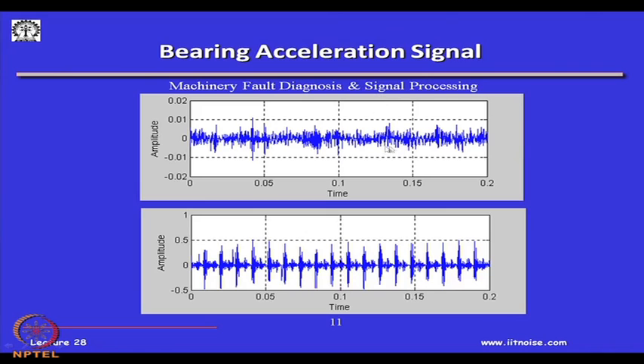And if you do the feature calculation from these signals, like the mean and RMS, you will see obviously the RMS value of this is much higher than this, but there are also factors like the kurtosis of the bearing signals. If I measure the kurtosis, you will see the kurtosis values of these bad bearings are pretty high, more than about 4 or 5, and then you can say for sure that this is a bad bearing.